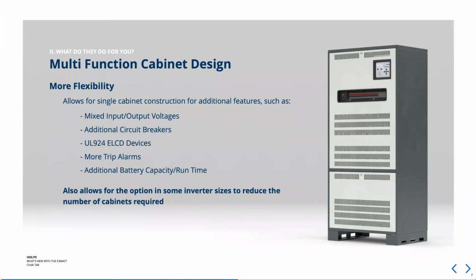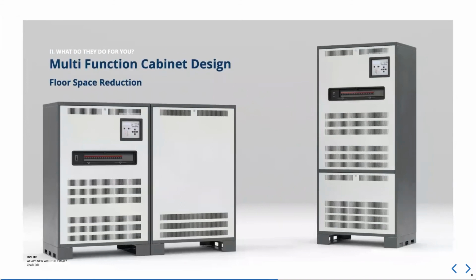That's super exciting. Another hot button this resolves is the move toward a design using less floor space at the cost of height. We can go from a system that used to take two enclosures down to one multifunction cabinet. You can see an 8 kVA system here with the two enclosures on the left, which can now be furnished in one taller enclosure with the same floor space requirement as one. We could do the same thing going from three enclosures down to two.